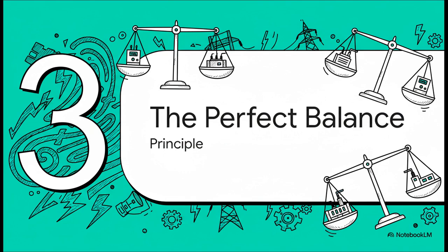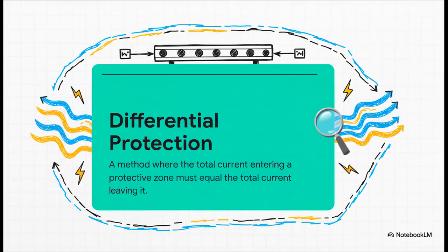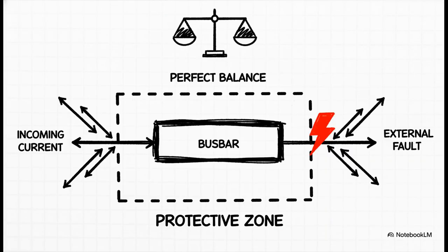Well, it all comes down to a really simple, almost beautiful idea. Let's call it the perfect balance principle. The technical name for this is differential protection, and it's brilliant. Basically, you create a protective zone around the busbar. The relays then live by one simple rule. What goes in must come out. The total amount of current entering that zone has to equal the total amount of current leaving it. Simple as that.